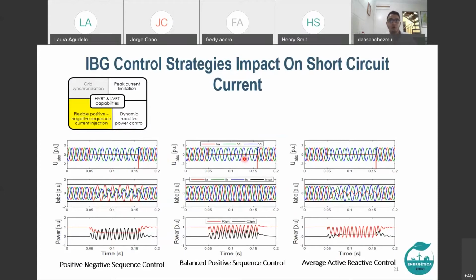Here we have an example of three different control strategies. First, positive negative sequence control. Second, balanced positive sequence control. And third, average active reactive control. However, these are not the only ones. In this example, a single phase to ground fault occurs. Check out this: the same PCC voltage, the same phase A short circuit, but we can see all three short circuit currents are different.